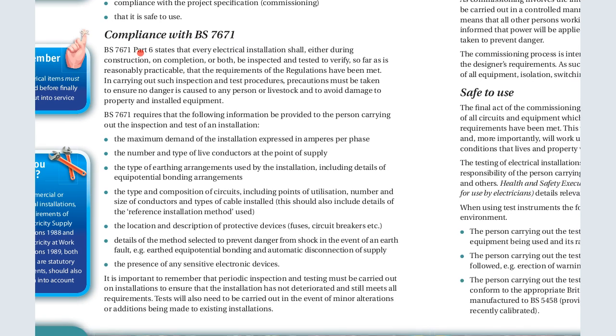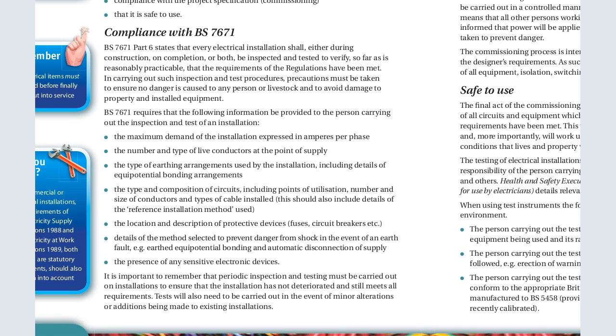In carrying out such inspection, test procedures and precautions must be taken. The BS standard requires that the following information be provided to the person carrying out the inspection and test of an installation. Number one is the maximum demand of the installation expressed in amperes per phase. We'll also look at the steps of testing and the instruments that we use to test. When testing, we make sure that the amperes per phase are in line, the number and type of live conductors at the point of supply, and the type of earthing arrangements. We also look at the composition of the circuit, including the points of utilization, the number and size of conductors, and the types of cable installed. Those are the things that are being inspected. The location and description of the protective devices, like the fuses and circuit breakers, has to be located, and then the details of the method selected to prevent danger from shock in the event of an earth fault.